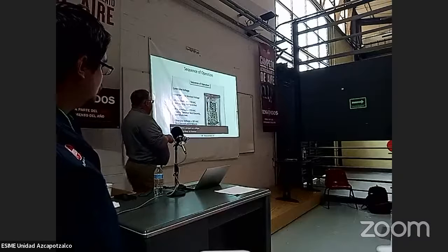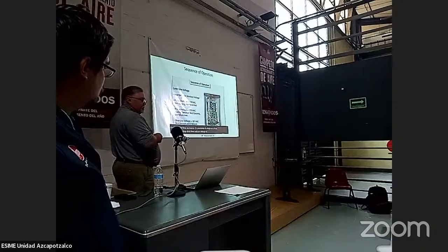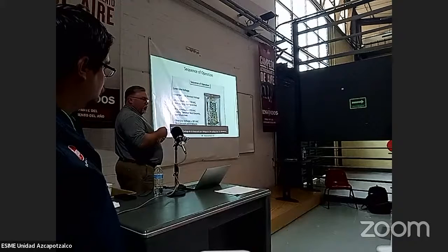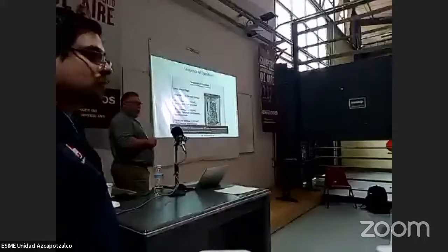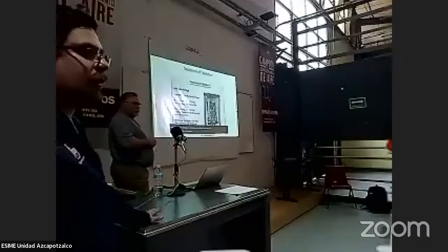On your line voltage, your inverter drive monitors your line voltage. So if the line voltage is below 179 volts AC, the unit will not start. Okay, so if line voltage is below 170 volts AC during operation for 4 seconds, the unit will shut down. Once the line voltage hits above 187 volts, 4 seconds, 3 minute time. Any questions on that? Una pregunta. ¿Sí entendieron más o menos la protección de temperatura que les había comentado? Bueno, aquí básicamente es de voltaje. ¿Sí?